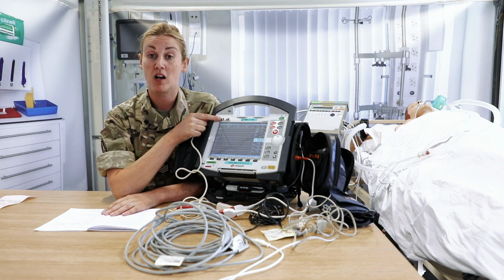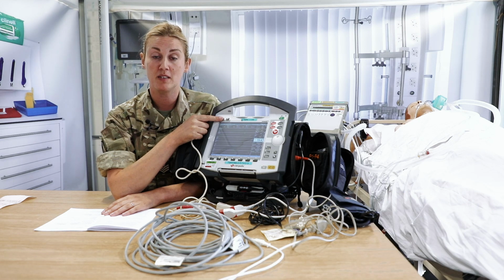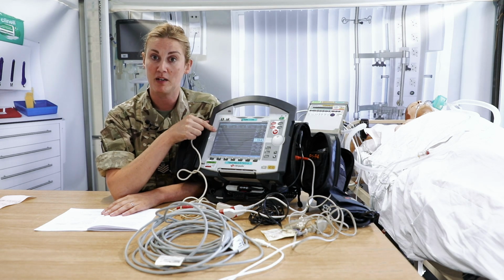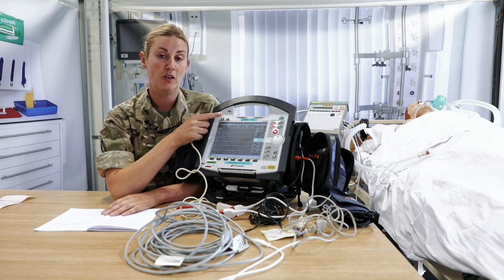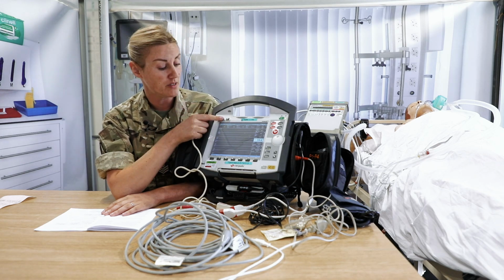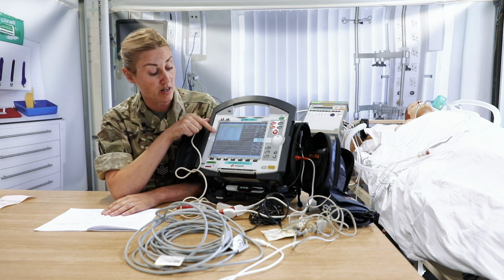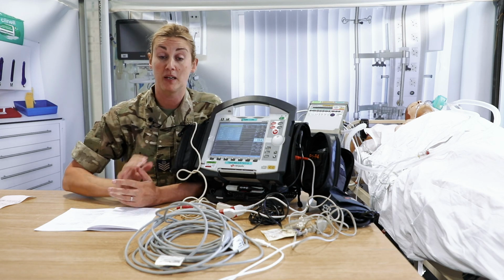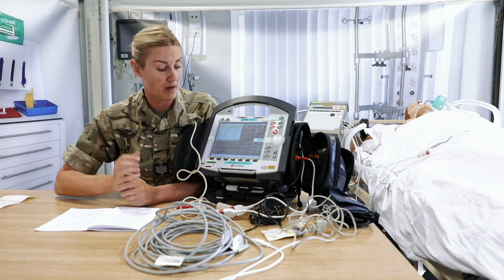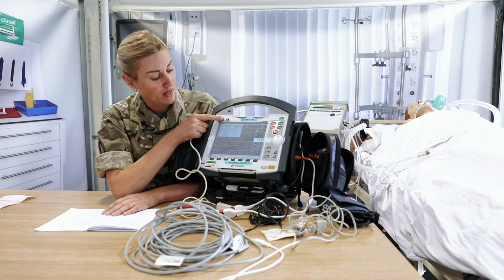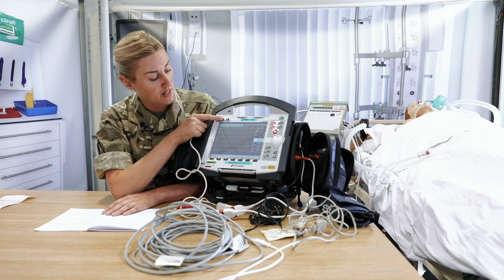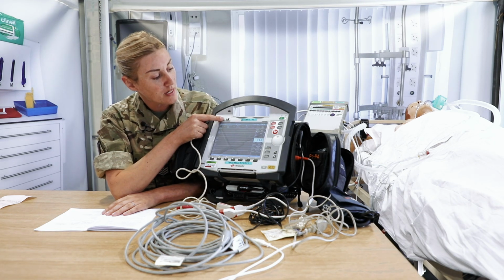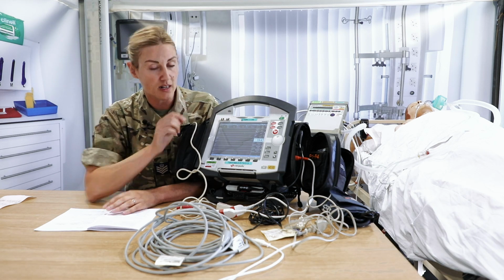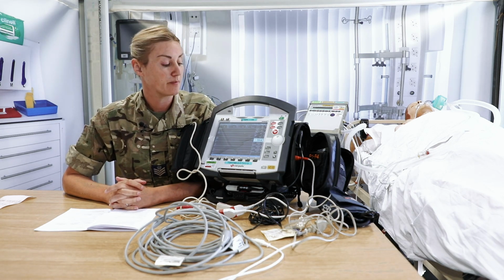At the top we have our alarm function, so pressing this button in the first instance brings up a list of the current alarms, and then you will press that to just get rid of alarms. There aren't any, so our current alarms are related to the fact that it can't pick up an end tidal, which is fine, I know about that. So I can just press it to get rid of the alarms, or I can press and hold it once and I get an alarm suspension for 2 minutes.